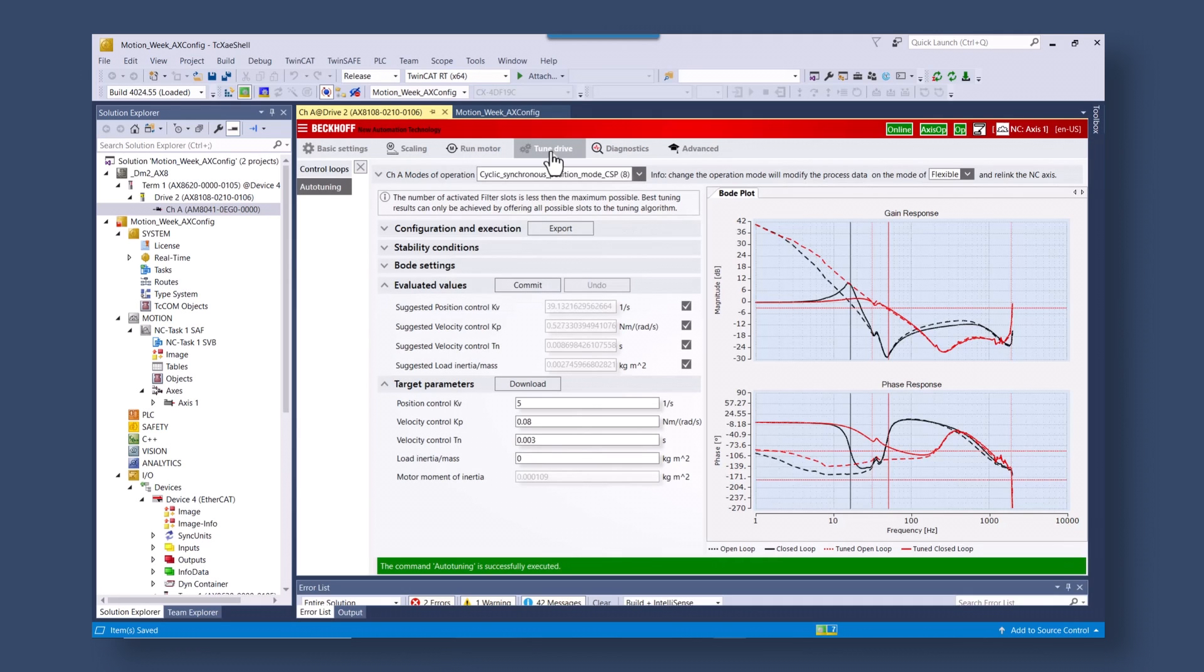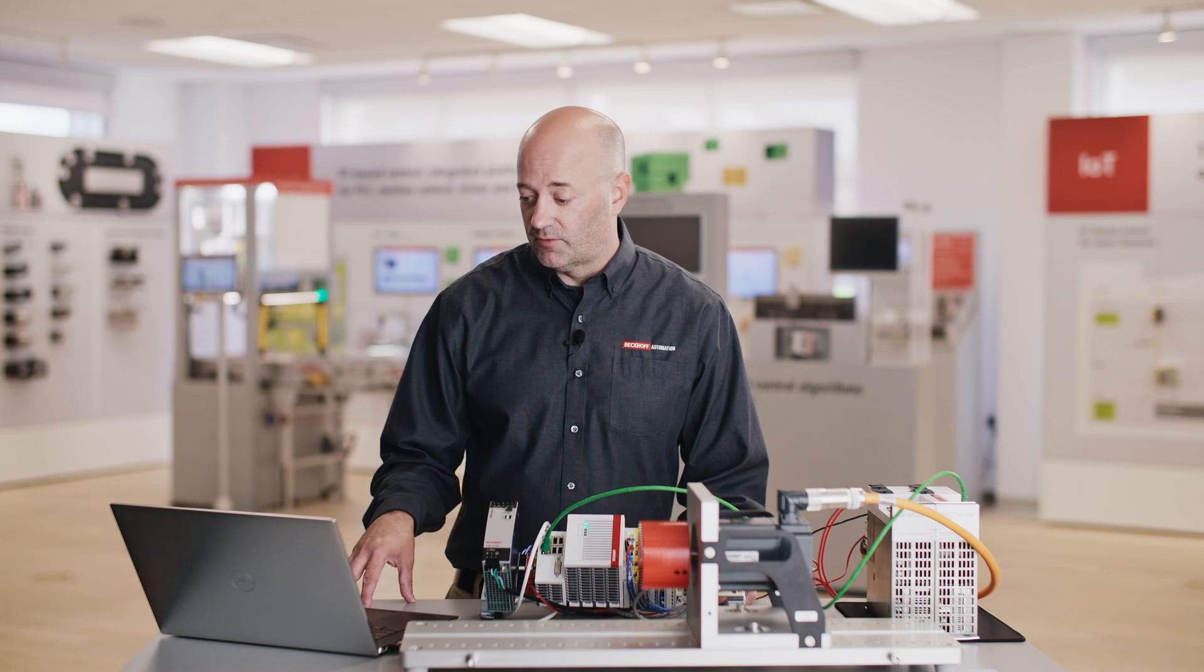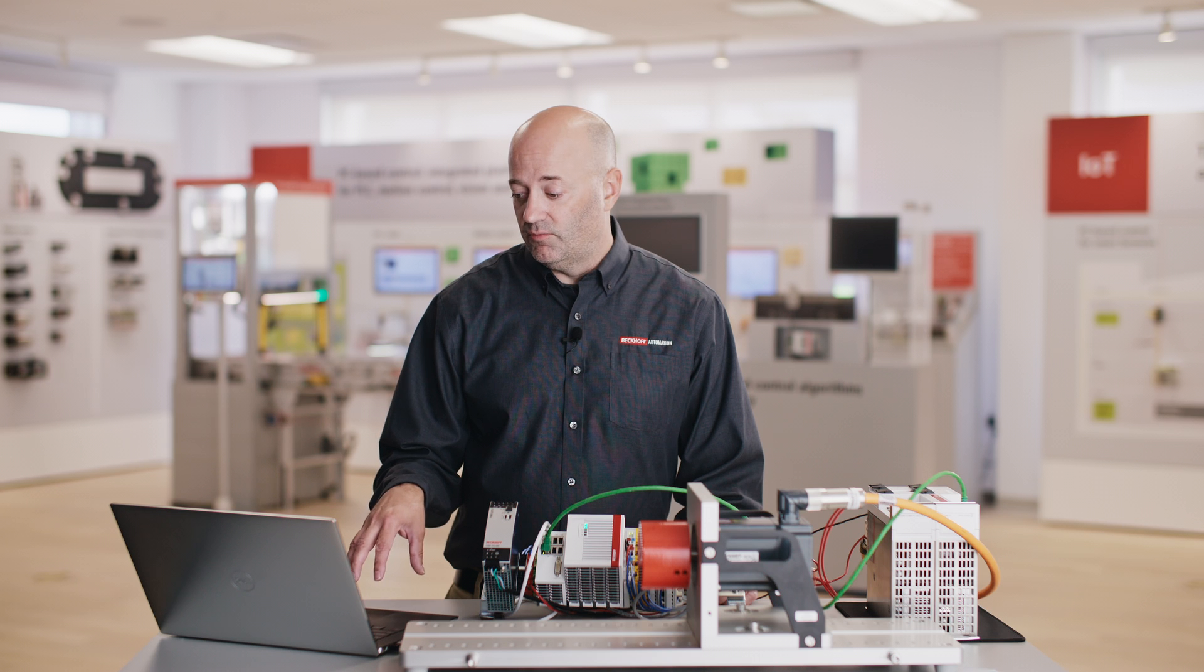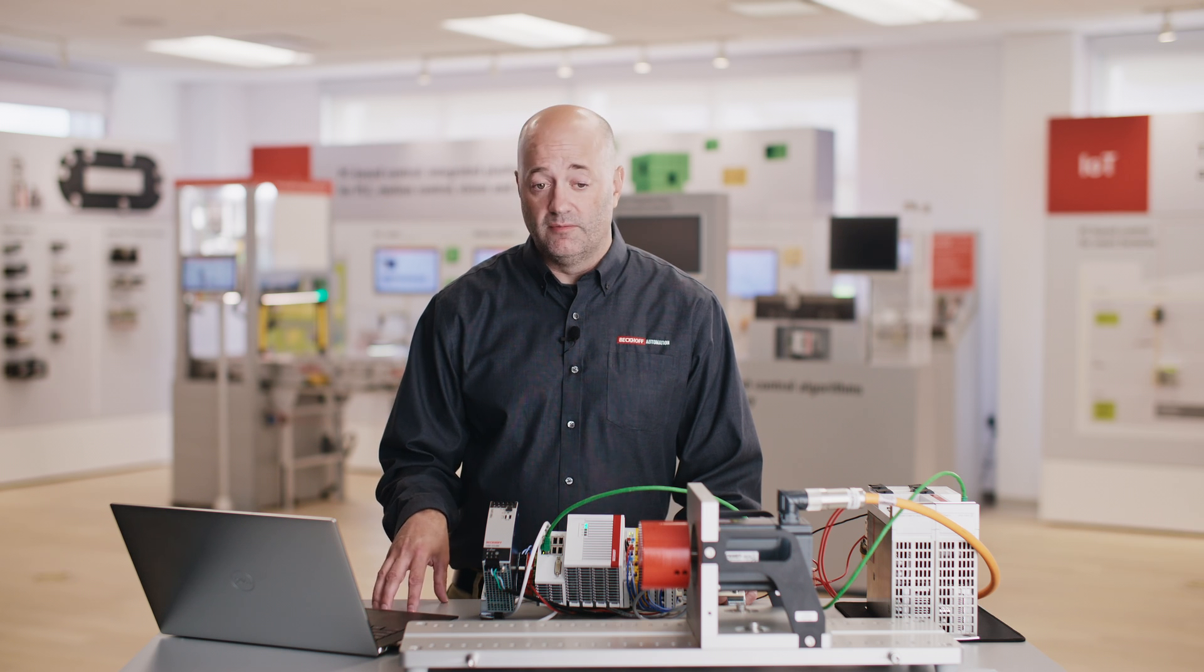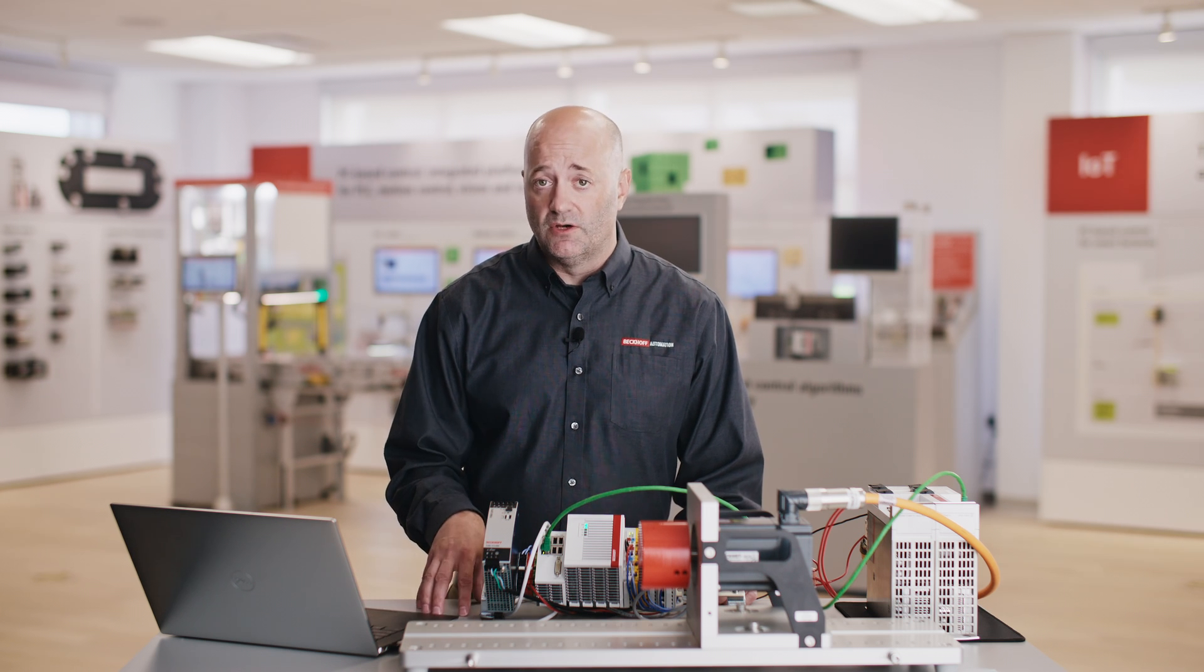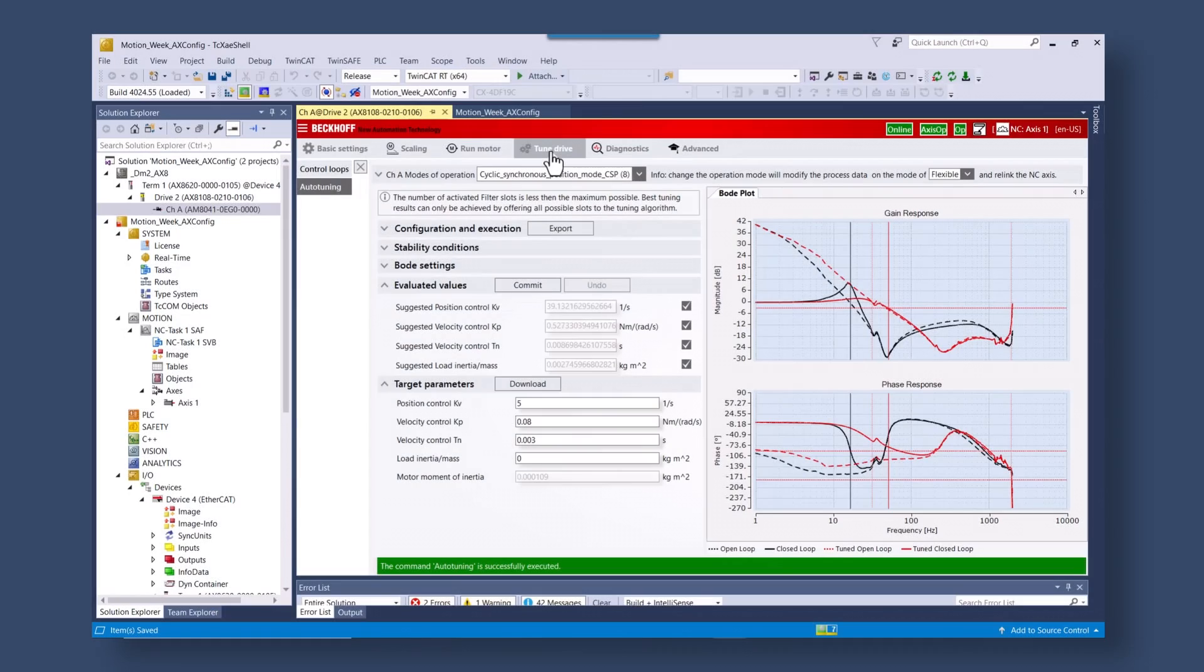So what you're seeing now is the results of the oscillation back into the bode plot diagram. So this is what we're going to use for the algorithm. And then once the algorithm gets results, it's going to reapply the parameters that it figured out, rerun the oscillation, and do a compare and give you the results.